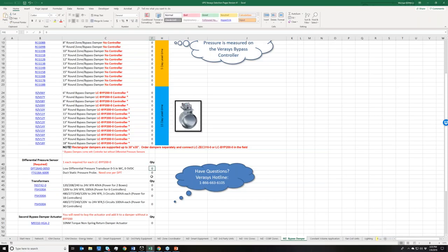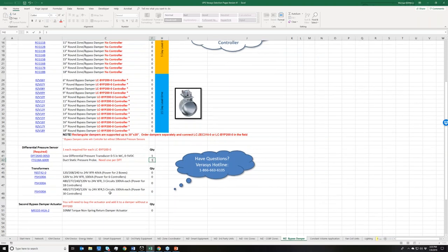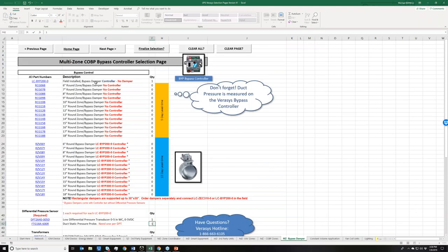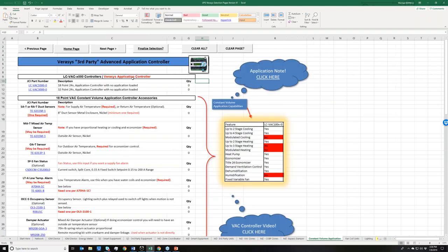Since it's not part of the assembly, I'm going to select one. I need one FTG per DPT, and then call it out here per bypass controller, so we're going to do that. If I wanted to do a slave bypass, where I have two bypass dampers serving the same rooftop unit, I would have to get another actuator. Again, you could use this one, but what I can't do is have two bypass dampers using BYP200 connected to the same rooftop unit.